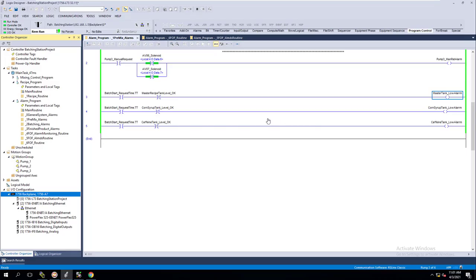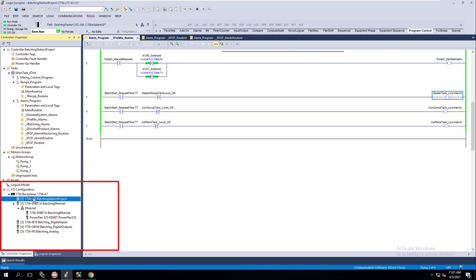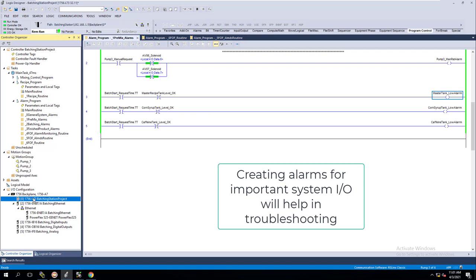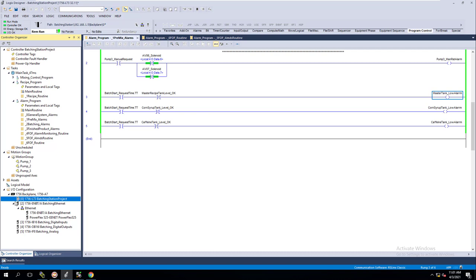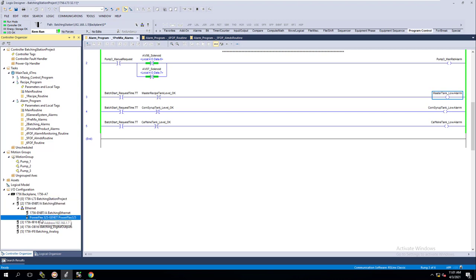We need to talk about IO faults and system support equipment faulting — our IO tree and IO configuration. If anything is critical to our system running, we want to understand exactly what's faulted and where to fix it. This helps engineers, controls techs, maintenance, and operations easily find where the problem is. We'll use GSVs to pull information from each independent device and then make an alarm for it.